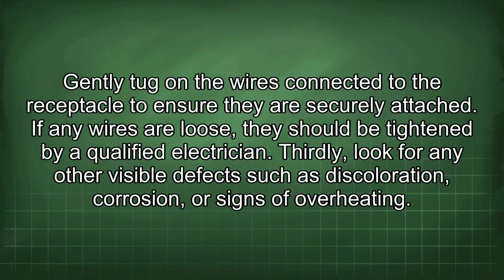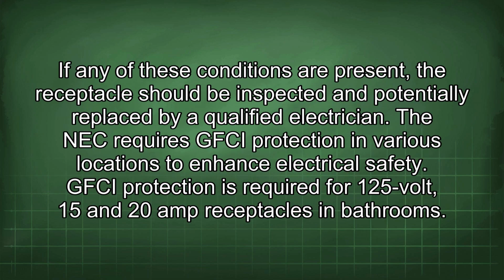Thirdly, look for any other visible defects such as discoloration, corrosion, or signs of overheating. If any of these conditions are present, the receptacle should be inspected and potentially replaced by a qualified electrician. The NEC requires GFCI protection in various locations to enhance electrical safety. GFCI protection is required for 125 volt, 15 and 20 amp receptacles in bathrooms.